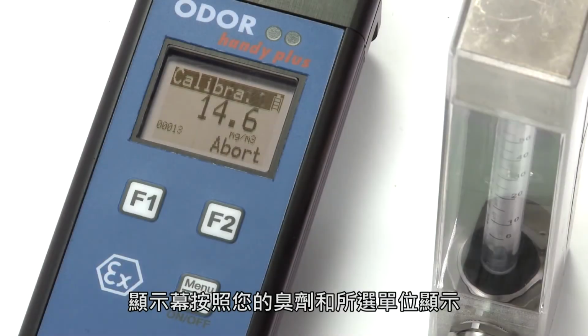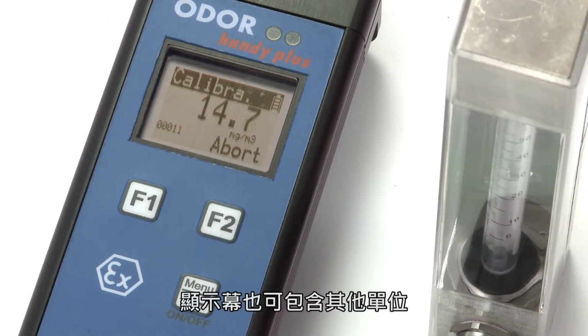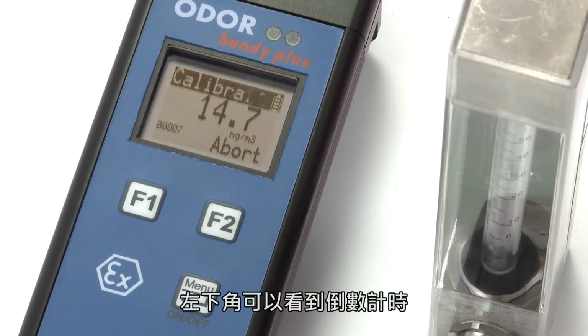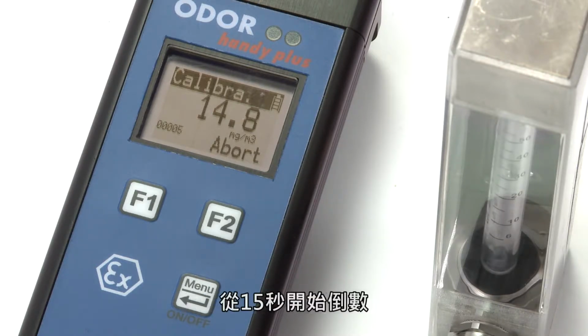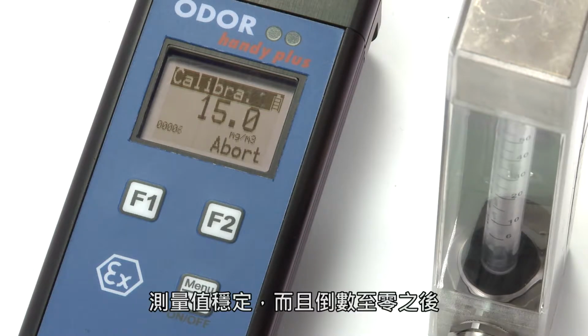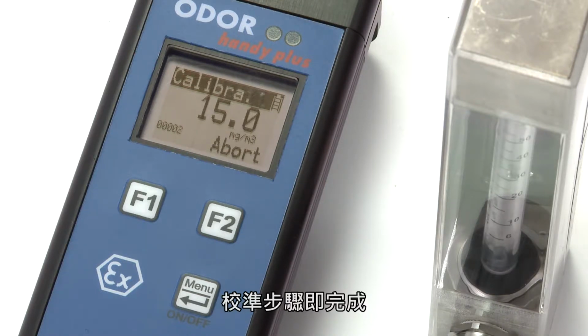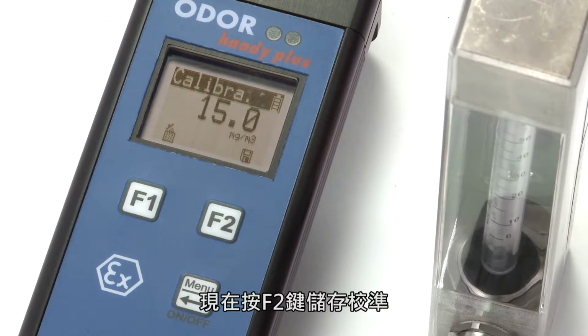Depending on your odorant and the selected units, the display can contain other units. In the lower left half, you see a countdown. This will be counted down from 15 seconds. As long as the measurement is still changing, the countdown will continue to jump back up to 15 seconds. When the measured value is stable and the countdown reaches 0, this calibration step is complete. Now press F2 to save the calibration.